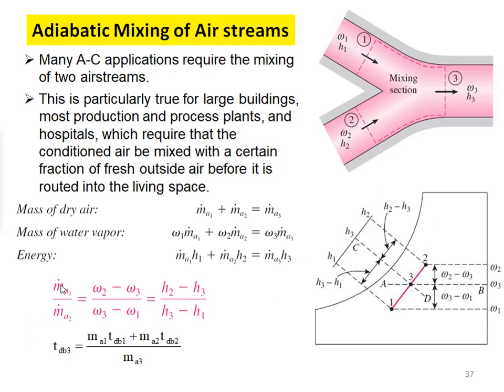From these equations: ṁ_a1/ṁ_a2 = (ω₂ − ω₃)/(ω₃ − ω₁) = (h₂ − h₃)/(h₃ − h₁). The dry bulb temperature at state point 3 is: T_db3 = (ṁ_a1·T_db1 + ṁ_a2·T_db2)/ṁ_a3. From this we can calculate the dry bulb temperature at section 3. These equations are used in adiabatic mixing, which commonly occurs in air conditioning systems.